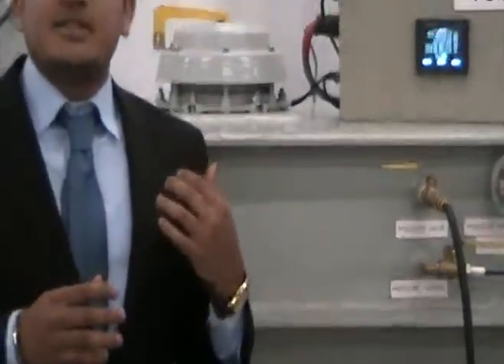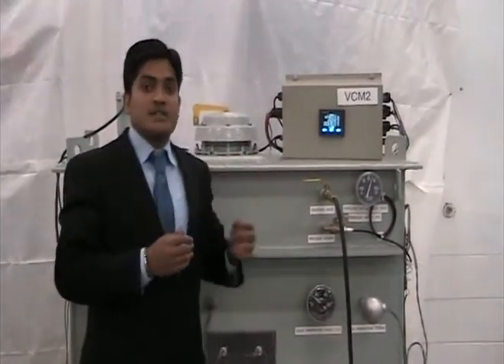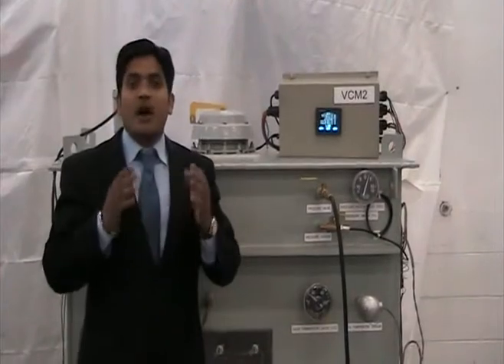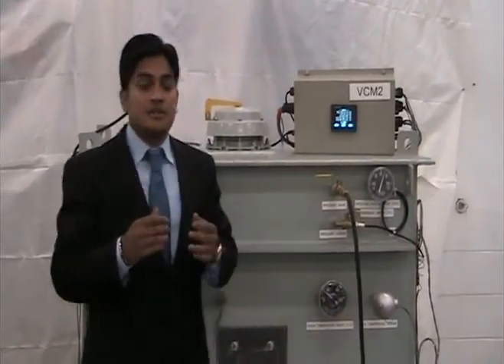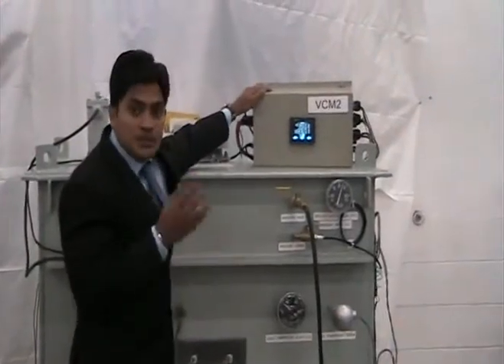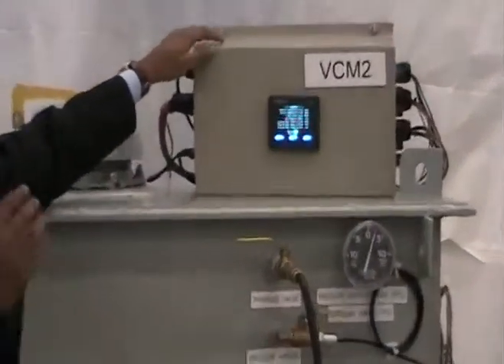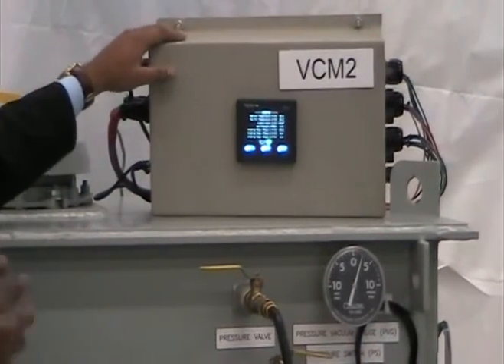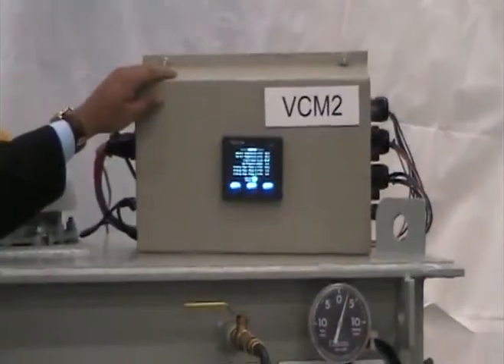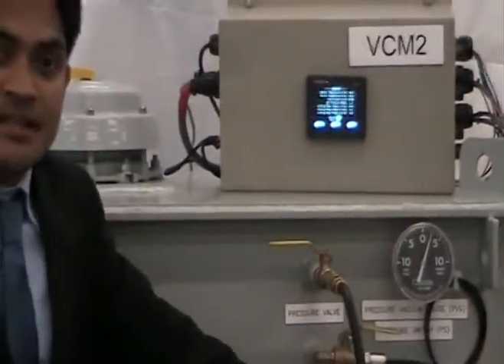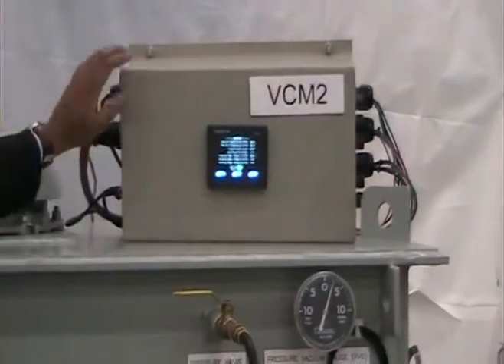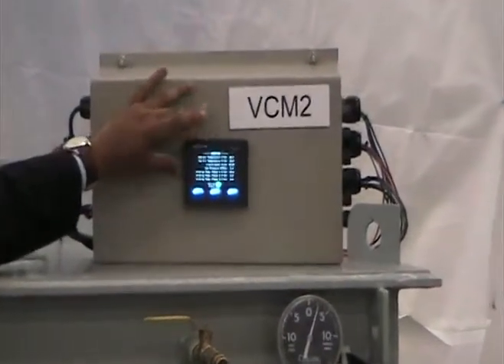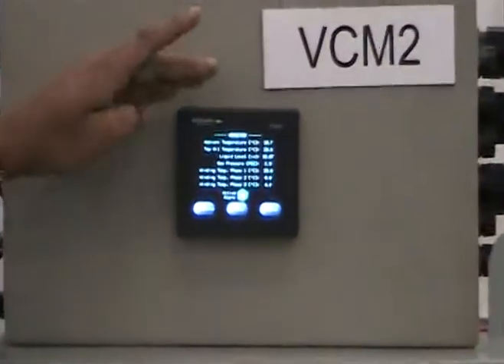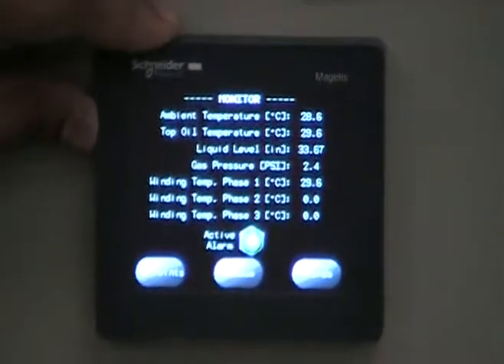The main purpose of this test setup is to compare and verify the gauge results with the VCM2 results and also to demonstrate how this VCM2 works under actual conditions. VCM2 uses various sensors to measure oil temperature, winding temperature, liquid level, pressure and ambient temperature. All the outputs from the sensor are connected to the VCM2 and various outputs are displayed on the screen. Based on the set points, the VCM2 activates the alarm contacts.